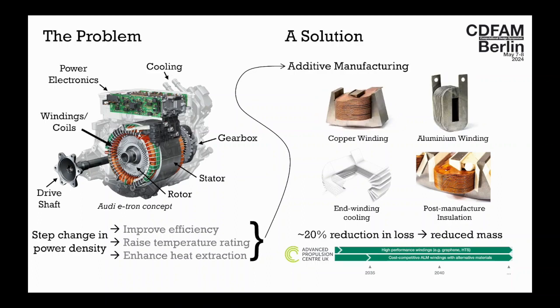So if we want to create step changes in the power density we can achieve, we need to do three things, ideally simultaneously. We need to improve the efficiency of the systems. At the moment, the winding, which is the mechanism that creates an electromagnetic field, is in the critical path, so we need to come up with ways of changing its topology and moving beyond conventional manufacturing methods to improve its efficiency and reduce the amount of heat we're generating.